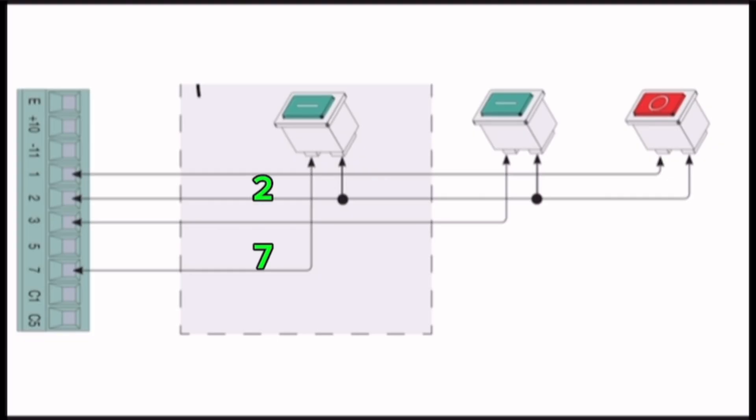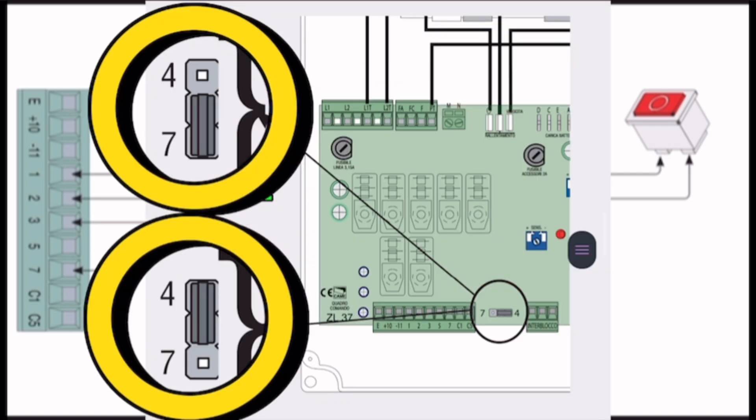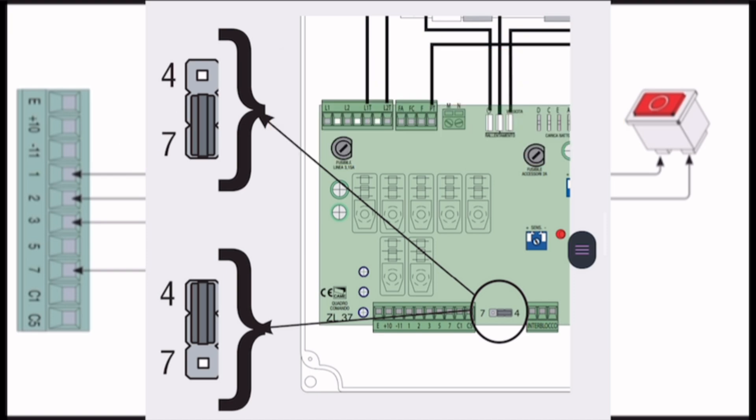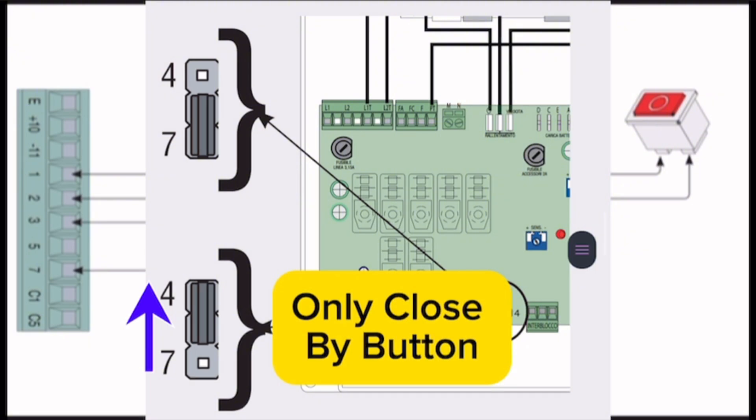Terminal 7 and 2 are NO Contact and use two different conditions. Condition 1: Open and close button. Condition 2: Just close by these two terminals. Check position of jumper between 7 and 4. If jumper near 7, this applies to open and close button. If jumper near 4, this applies to condition 2.